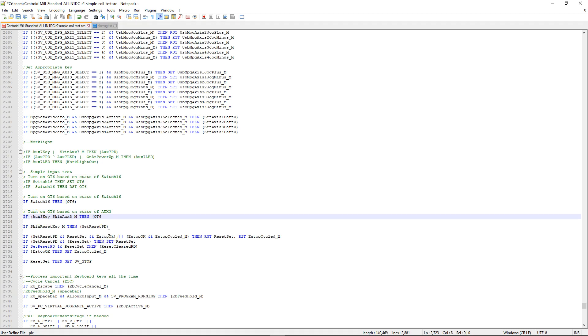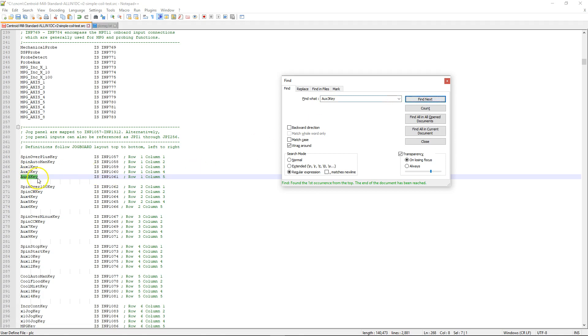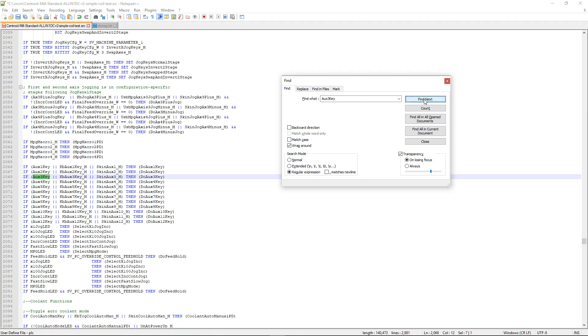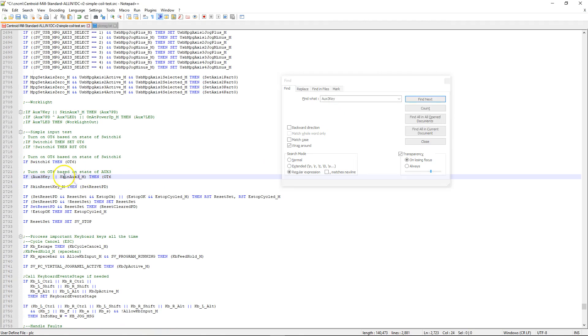I can have it where either of those two conditions will be set by adding an OR in there. This means either the physical button — which is AUX3 key — or the skin event of AUX3, which is used from the virtual control panel. If you search for AUX3 key, you can see it is physically an input tied to input 1061. So either that or the skin event — whichever condition is met — will turn on OT6.